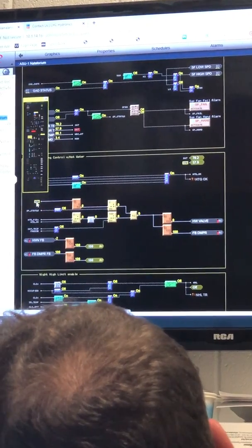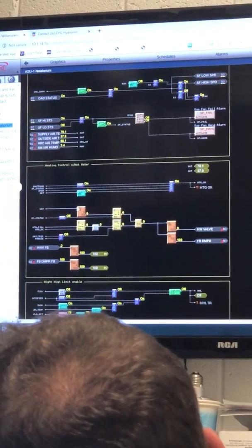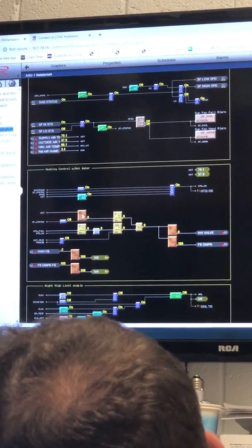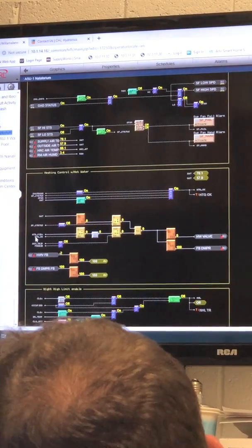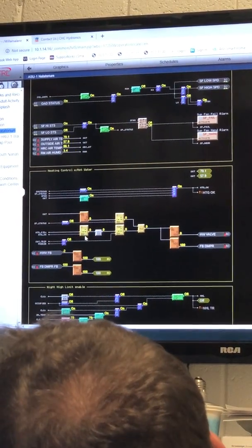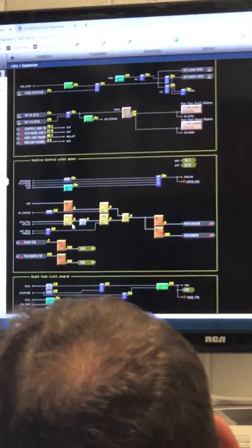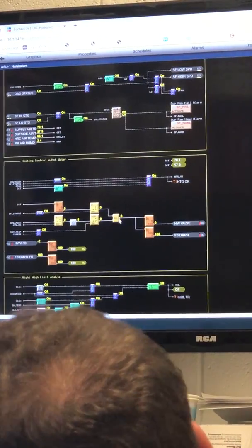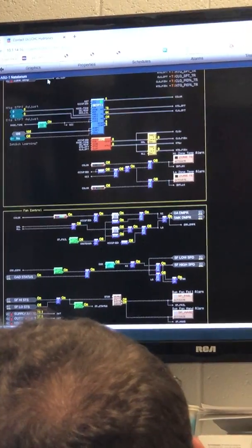So if outside air temperature is between 32 and 10, so it's higher than that, that's going to produce a 0. This switch will be 0. So when the heating PID comes in here, if heating is in the OK zone, it clicks this switch, which gives me a 0, so that's what's happening. It's basically within the dead band right now.